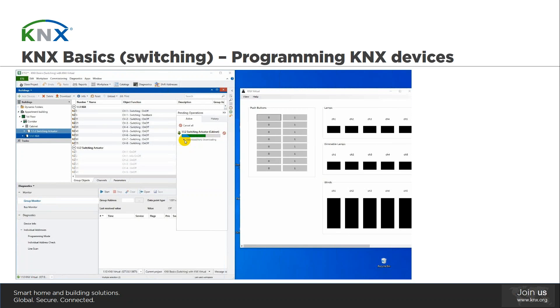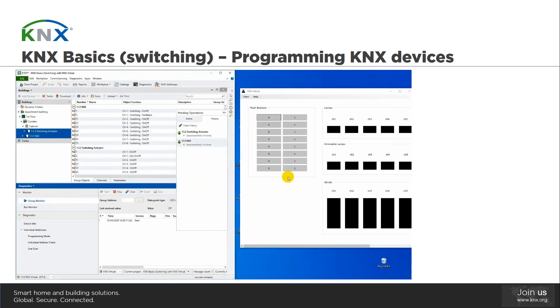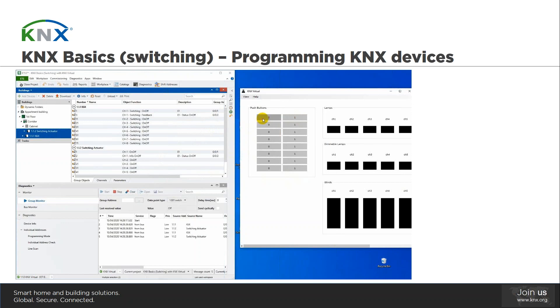What we still need to do is program the devices again to activate the extra functionality. A partial download is sufficient because the individual address is already programmed together with the application program. To save time, I select both devices and perform a partial download. After the download is completed, we can see that if we manipulate the rockers, the color of the text on the button becomes red, indicating the lamp is switched on. Clicking the left rocker, the color becomes black again, indicating the lamp is switched off. We then start the monitor to see the message exchange between the push button and the actuator. A telegram from device 1.1.1 and group address 001 is sent to the bus with value ON, and then another telegram comes from device 1.1.2 and group address 002.